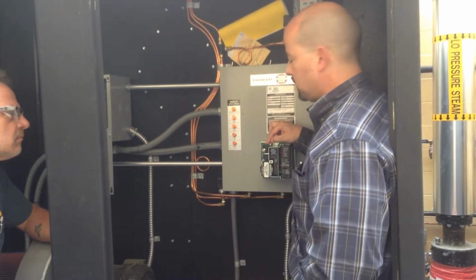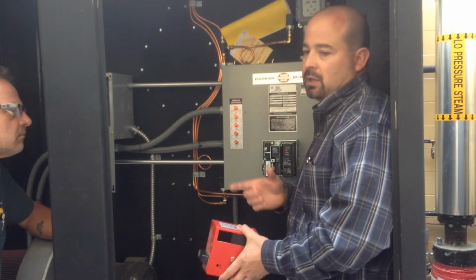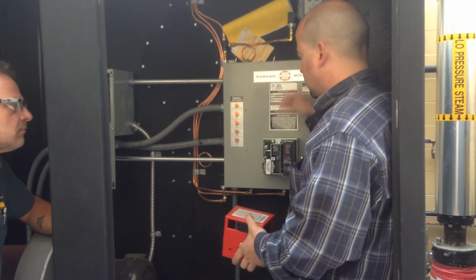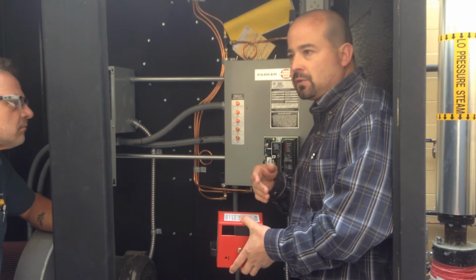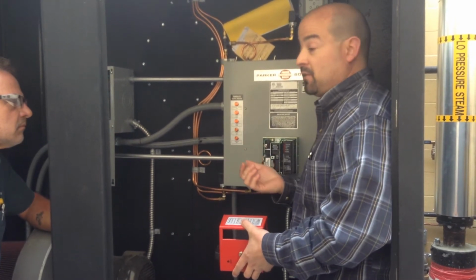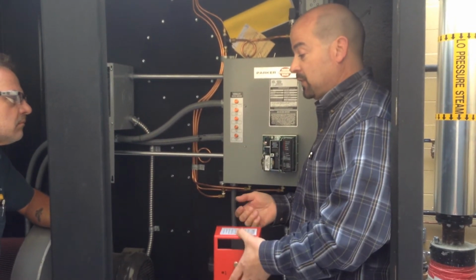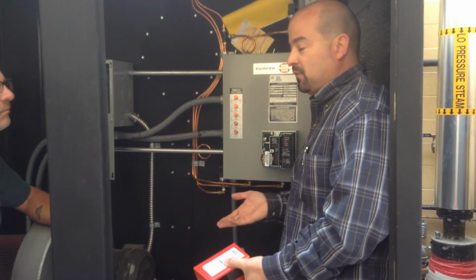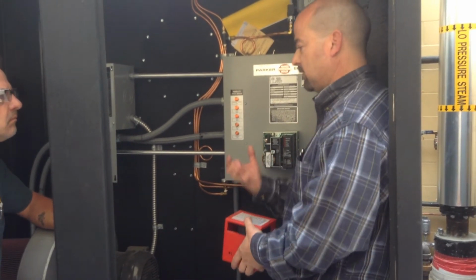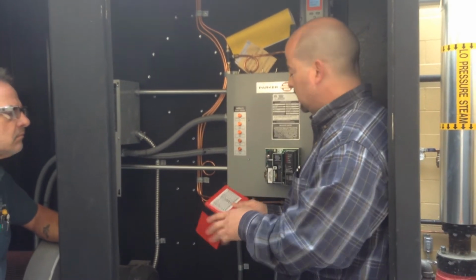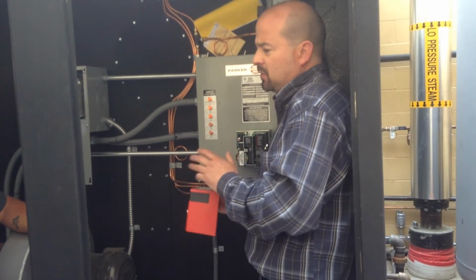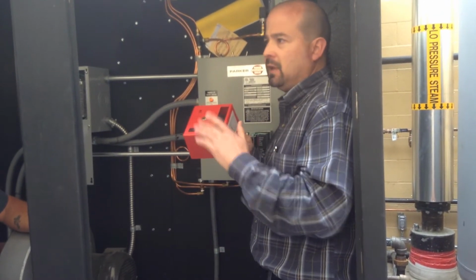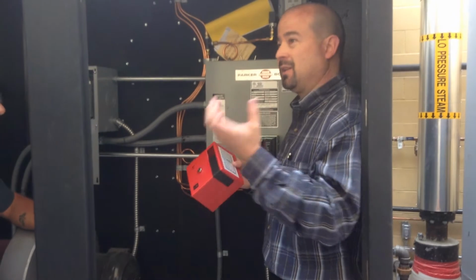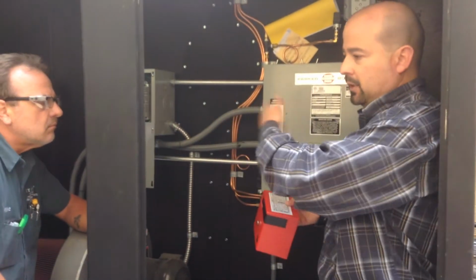And there's an RJ45 connector here. So the optional display module, you plug it in and it saves the last 6 faults so you can see what the faults are. If you wanted to see what the flame signal is, you feel like it's intermittently flame failing, you want to test the pilot, you can see the flame signal. But if you don't have that, which I don't think you really need unless you had a multitude of these controls throughout the campus, then you just have one and plug it into each boiler.